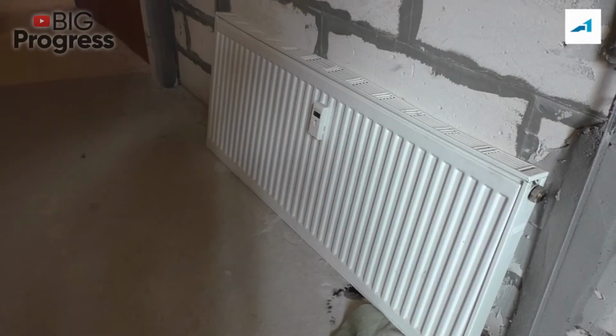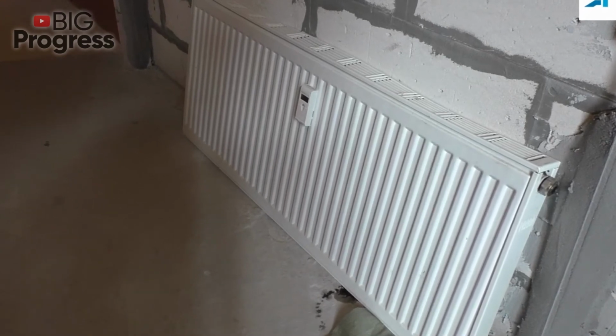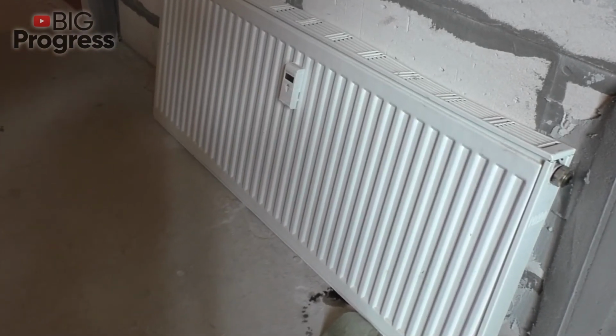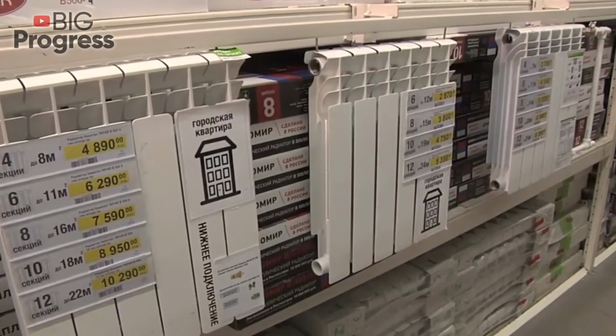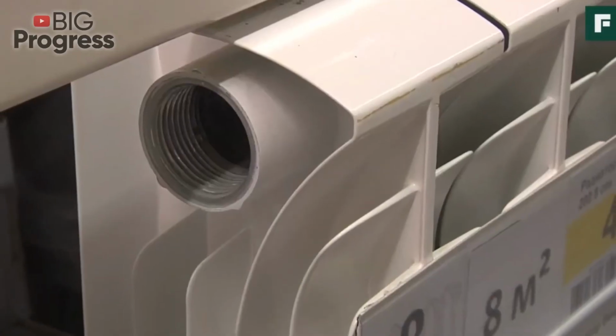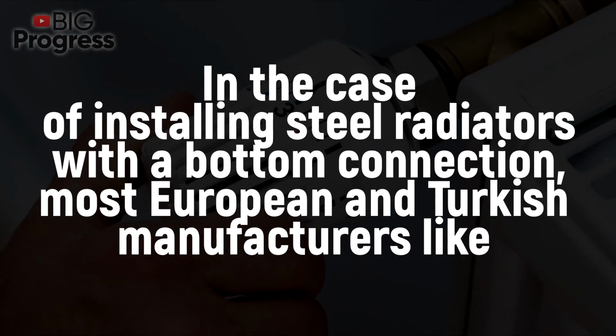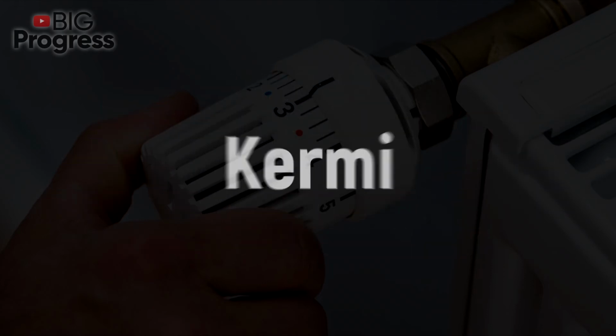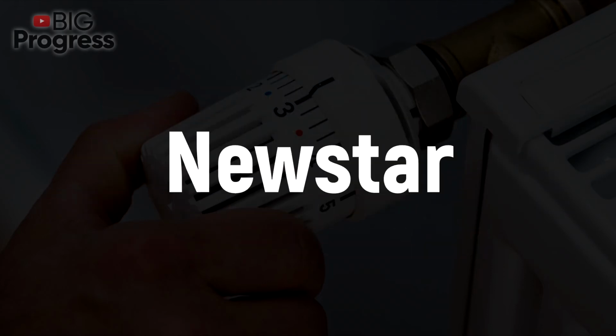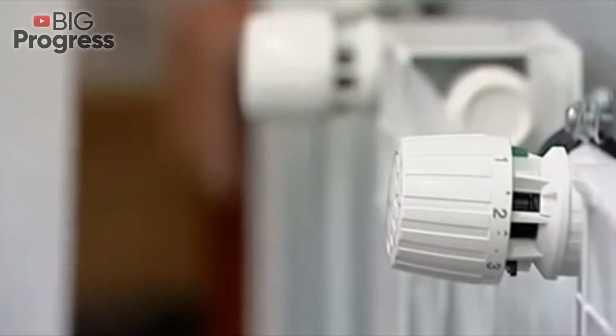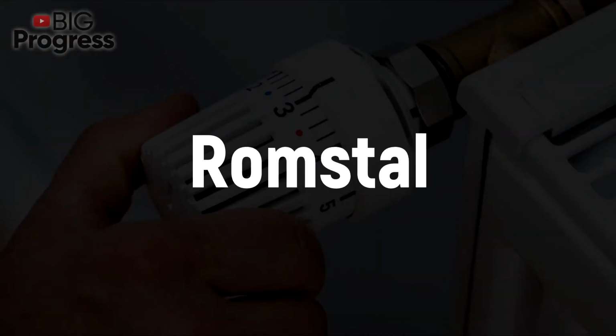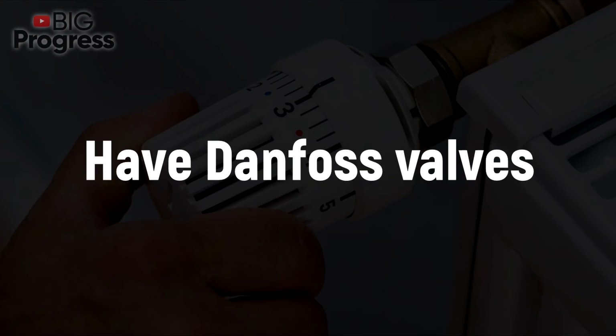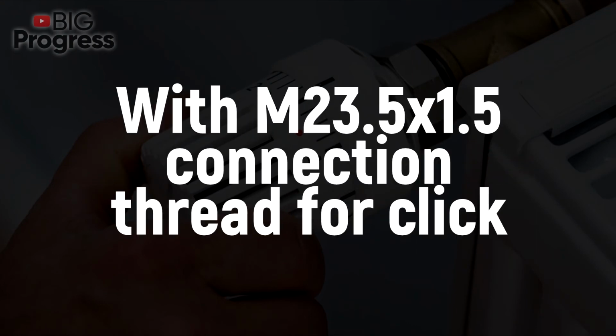Heating radiators. If you have installed steel, aluminum, bimetallic, or cast iron radiators with side connections, then you just need to determine what connection thread the thermostatic valve connected to the radiator has. In case of installing steel radiators with a bottom connection, most European and Turkish manufacturers like Kermi, Purmo, Korado, Hanrad, Newstar, ECA, and Karad have Ventil valves with a universal thread M30 by 1.5. Vogel and Noot, Romstal, and Regulus radiators have Danfoss valves with M23.5 by 1.5 connection thread for click.